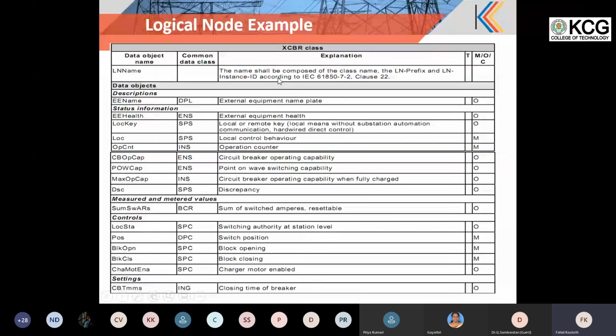Then position is one of the parameters, which is the switch position. It refers to double point controllable. It is a common data class. You can see position is a double point controllable common data class. So in order to get the details of the position common data class, you have to refer to 7-3, DPC, double point controllable, and the details of the DPC will be there under that. And you can see mandatory, optional or conditional can be there in this, and position you can see is mandatory, that is, any device manufacturer who is supporting XCBR needs to have position as a mandatory element. That is given as mandatory.